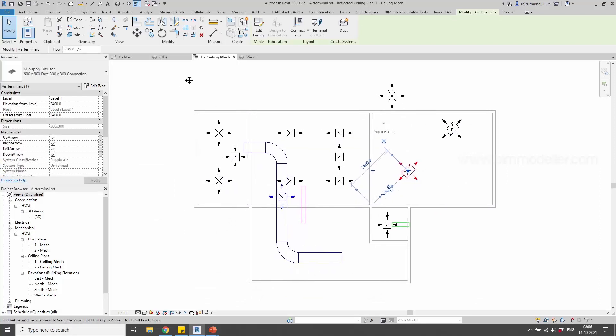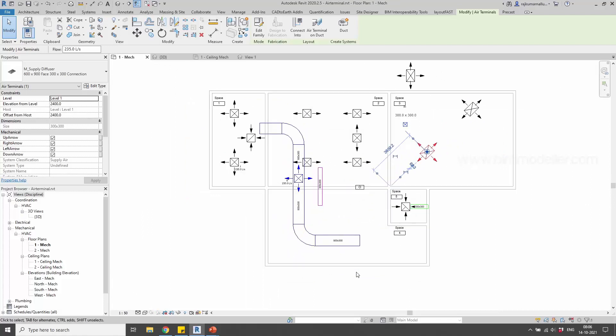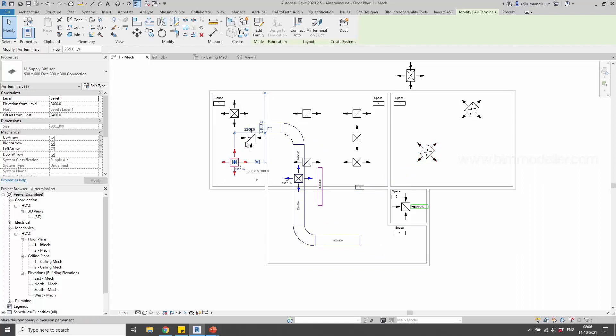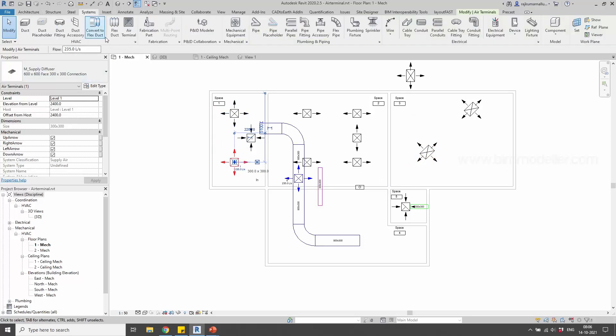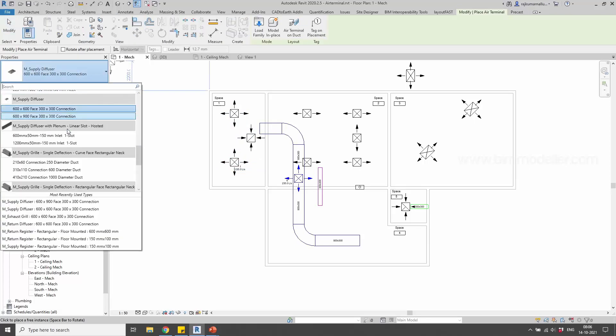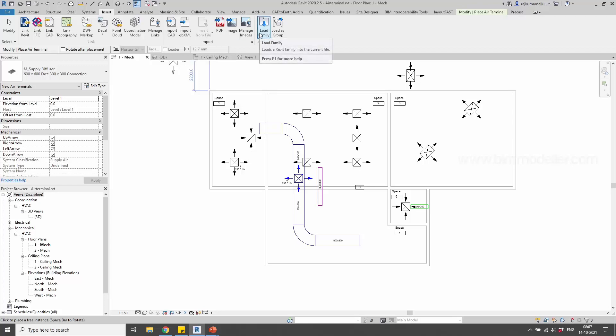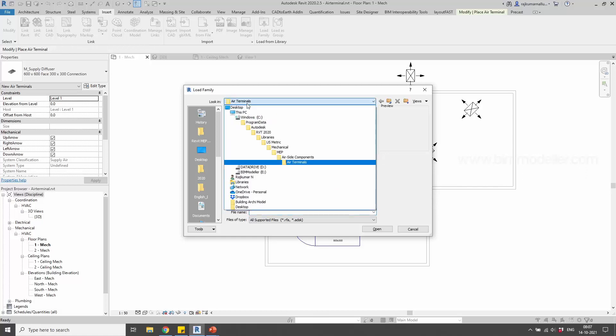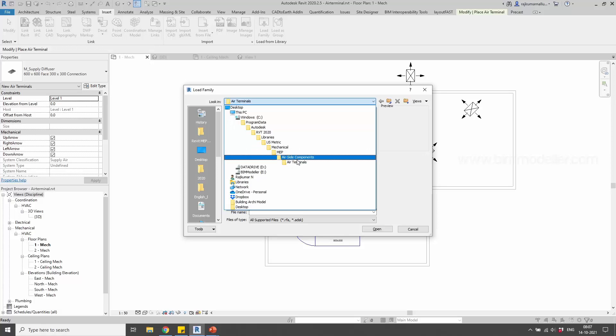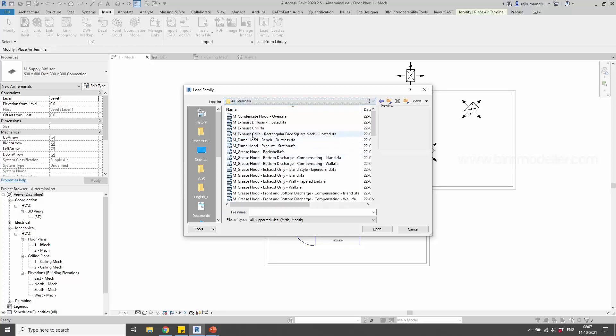Some grills may need to be placed on the wall or on the floor. In that case, you need host-based elements. The elements we have placed so far are non-host elements — we can place them at an offset height. If you need a new air terminal, after selecting Air Terminal you can load from the Revit library, or under the Insert tab use Load Family. The library path is: Autodesk > Revit 2020 Libraries > US Metric > Mechanical > MEP > Airside Components > Air Terminals. Select whatever air terminal you need and load it into the project.